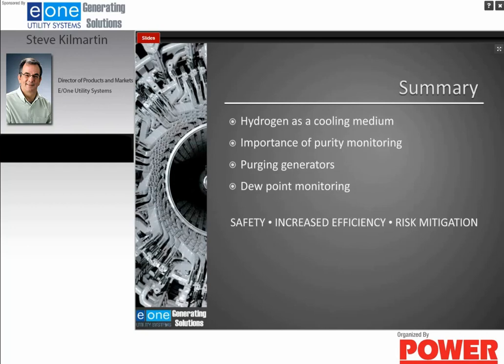Our P&ID is correct. Our valves are labeled correctly. When we are measuring dew point, we're mitigating risk. High dew point in generators can lead to component failures. All of this is about safety, increased efficiency, and risk mitigation.